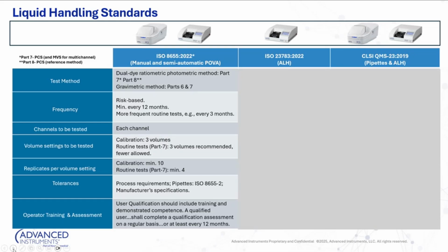And then last but not least, ISO 8655 Part 10 came out in 2024. That's all about user qualification, user training, and assessment. That particular standard indicates that any pipette user or any user of a POVA should be trained, that's important of course, and should be consistently assessed and monitored at a minimum of every 12 months. So those operators that are using those pipettes, maybe your pipettes are being calibrated and they perform beautifully after they're calibrated, but if you place them into the hands of an operator who doesn't know how to use them in the most ideal fashion, you're not going to get the best results you can. So making sure that you have those records on hand is important.